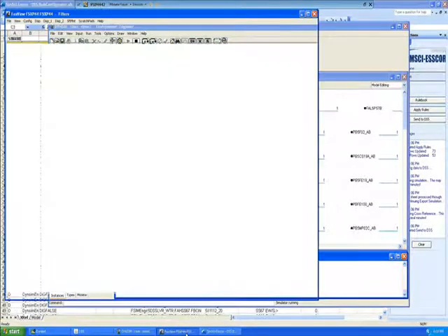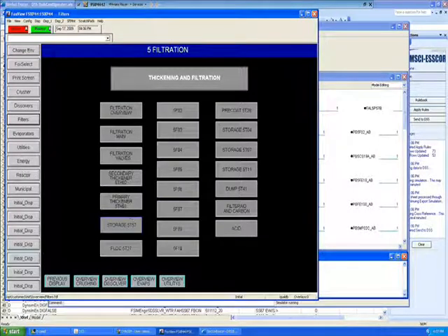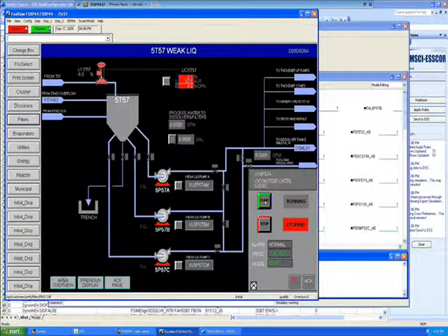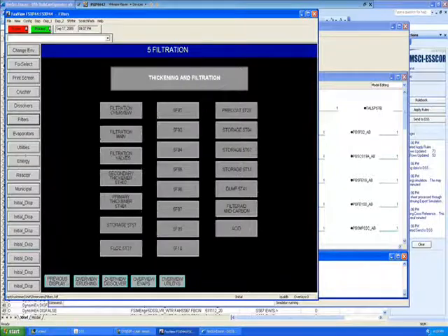The rulebook we used had entries to create tieback models for motor start-stop logic and flow control. Here we demonstrate the proper functioning of the motor by pressing the start button, which sends a command out to the model, which then loops back to the motor running status input. Therefore, we can test that the interlocks on the motor are satisfied.